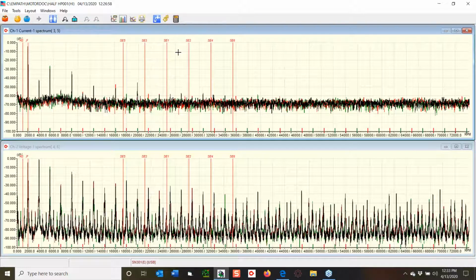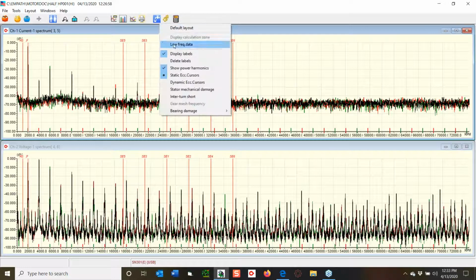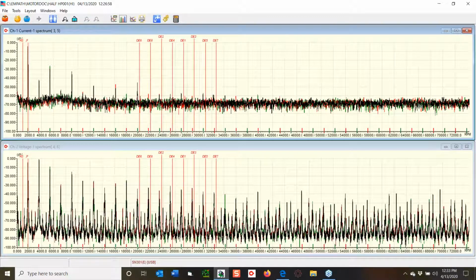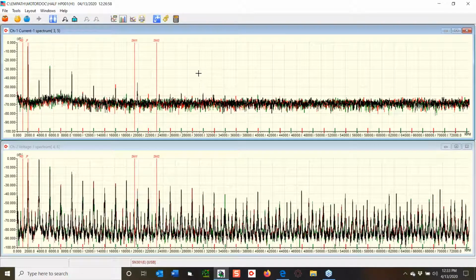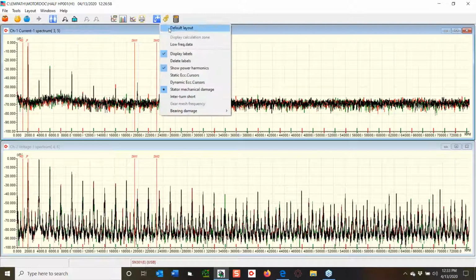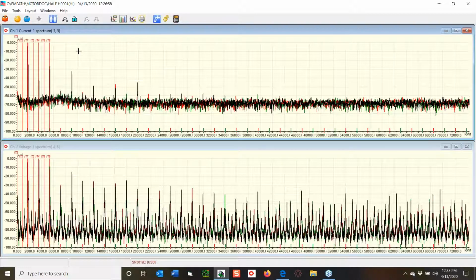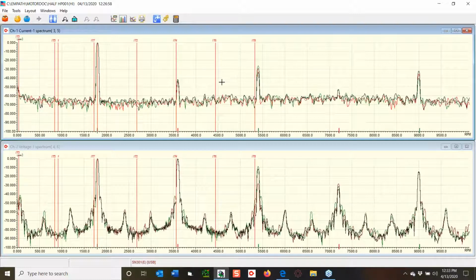Nope. Let's see if any of these are power harmonics. If I have power harmonic peaks, those don't count. Dynamic, meaning an orbiting rotor — nope. Stator mechanical issues, basically meaning do I have a winding issue and so on. Interturn short, and that's the one we'll talk about later. If I don't have a well-tuned drive, I will get peaks. Okay, not seeing them. Considering I don't have a well-tuned drive, it's pretty cool that I don't.